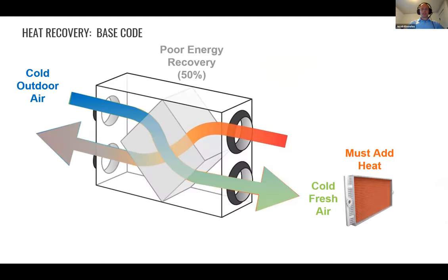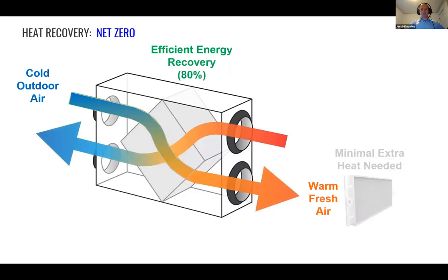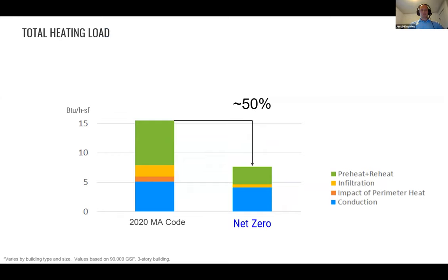Another key element is ventilation energy recovery — it's a huge driver of building energy consumption. If you go from a conventional heat recovery system to a more efficient one, you can save energy and greatly reduce or even eliminate your heating demand in wintertime. You can recover so much energy from exhaust air before it leaves the building that some systems don't even need to add more heat to incoming air — just recovering that energy gets it warm enough to bring into the space as fresh ventilation air. This way you can achieve goals like a 50% heating load reduction compared to a conventional code-minimum design, which is a game changer for moving towards net zero cost-effectively.